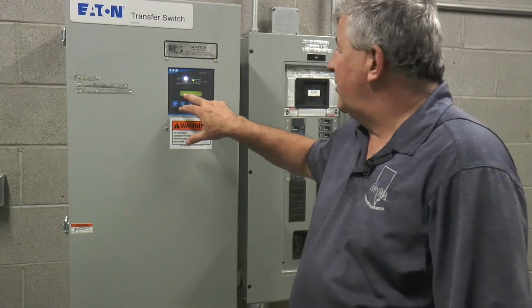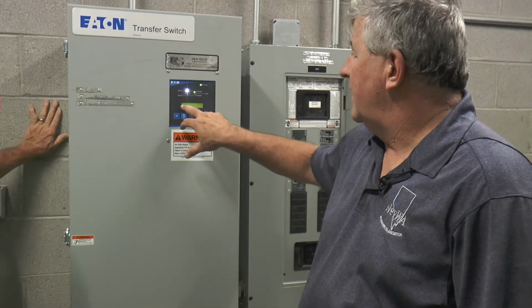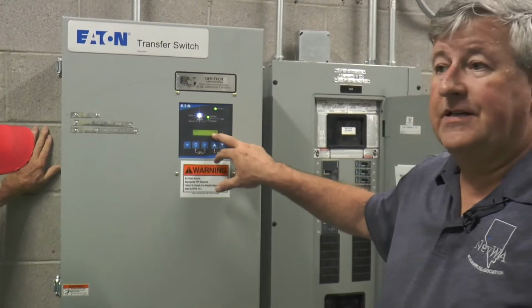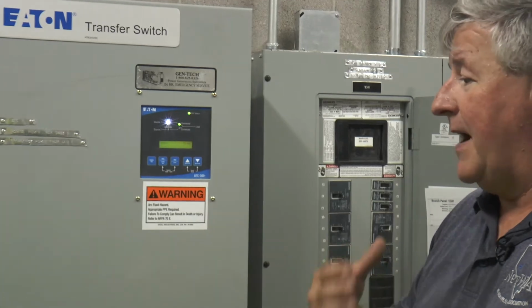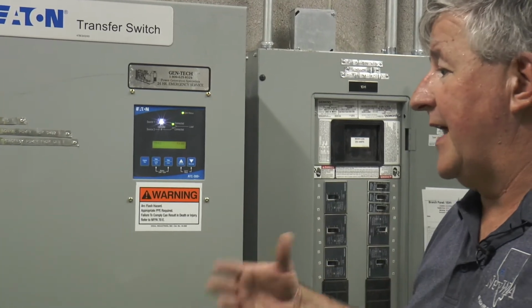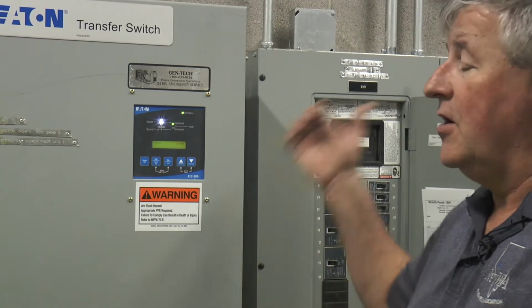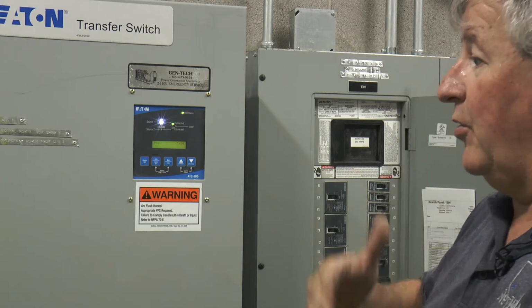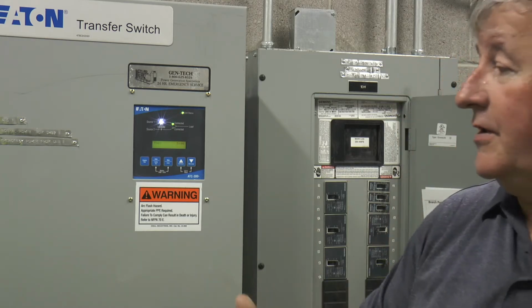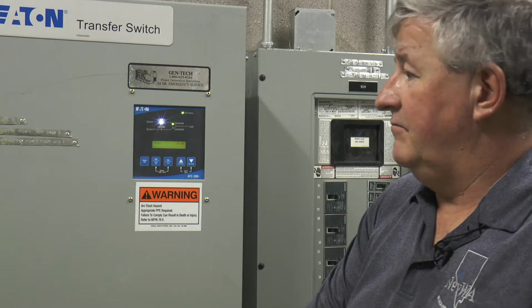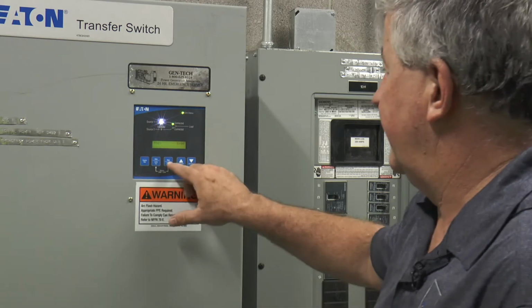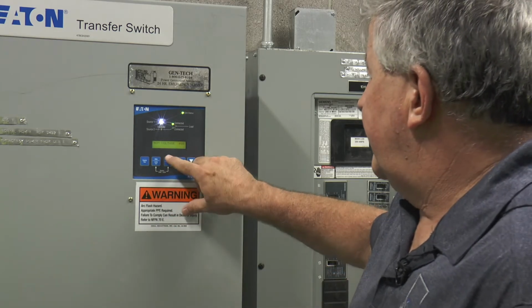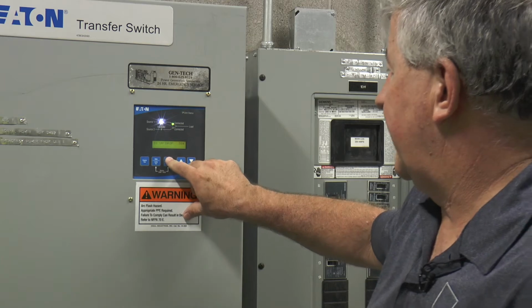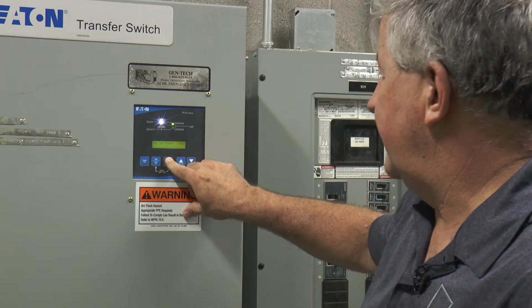Okay, the next, emergency to normal, is 10 minutes. Time delay engine cooldown is set for 5. So upon retransfer of both transfer switches, the last switch that goes back to utility will tell the generator to shut down. It will run for 5 minutes at a no load condition and then shut itself down and wait for the next event. Then frequency, nominal voltage, source pickup, and dropout for your voltage settings.